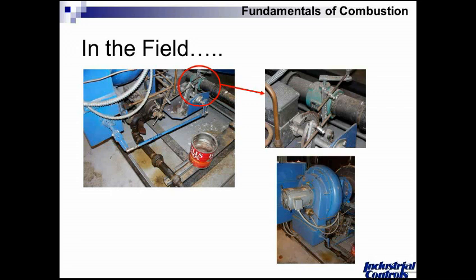By linkageless, I mean we actually provide an electronic servo motor to go on the damper shaft for the combustion air. And then there's another motorized servo which goes on the fuel control valve. Those two servos are electronically connected to a brain that maintains the fuel-air ratio precisely where you set it.